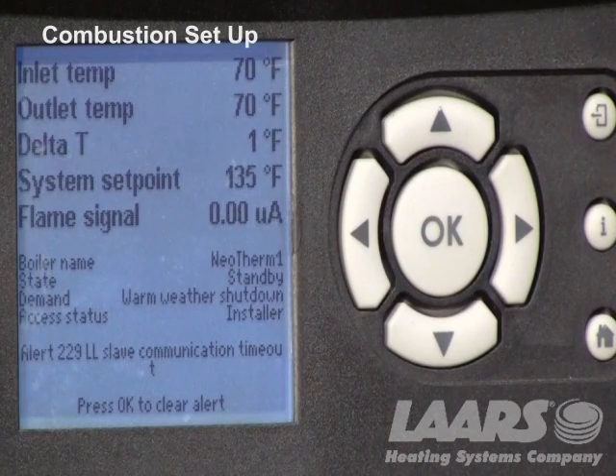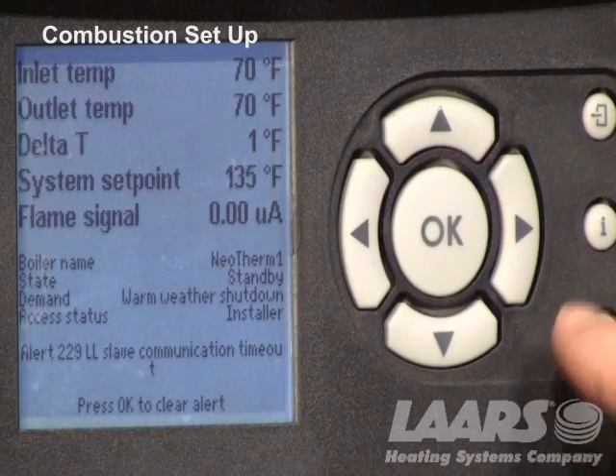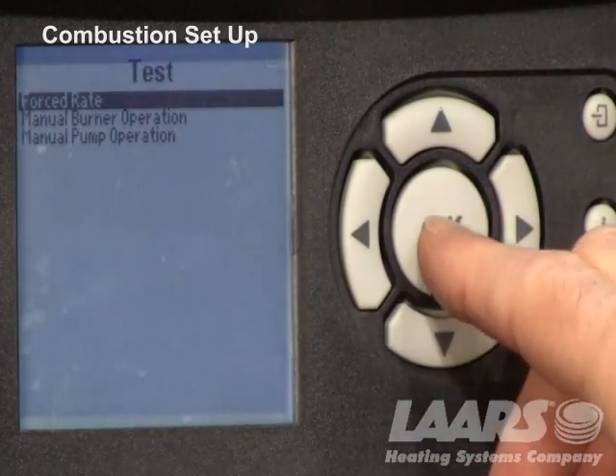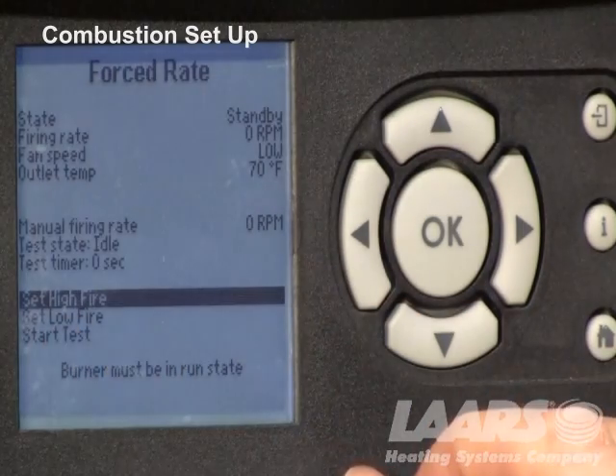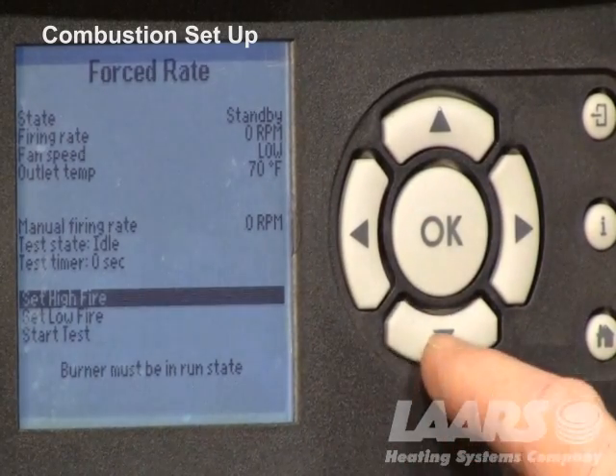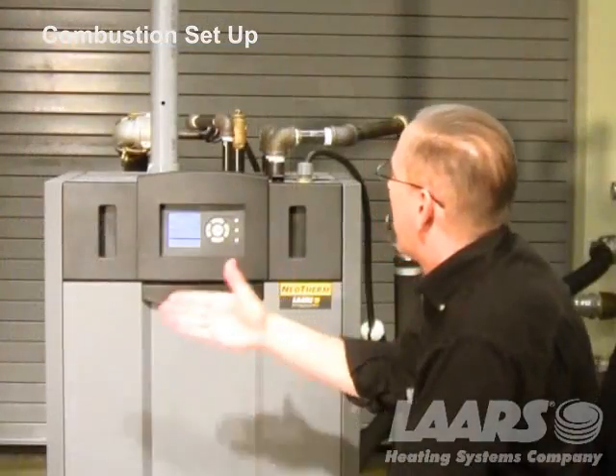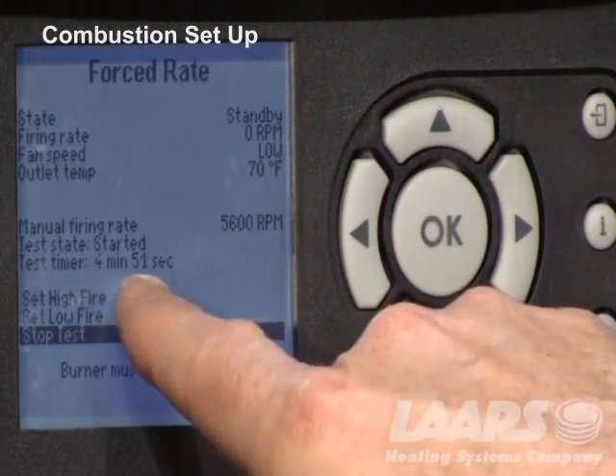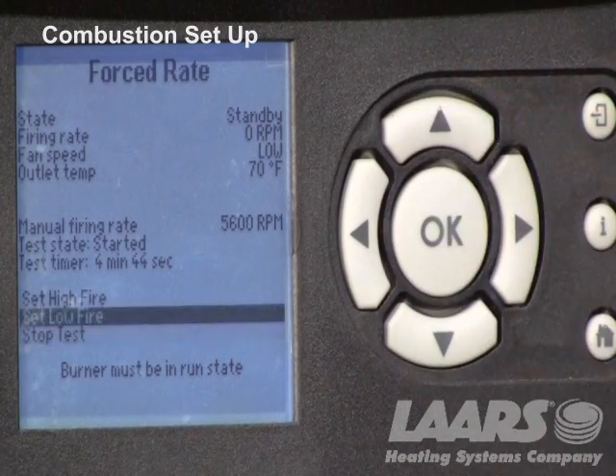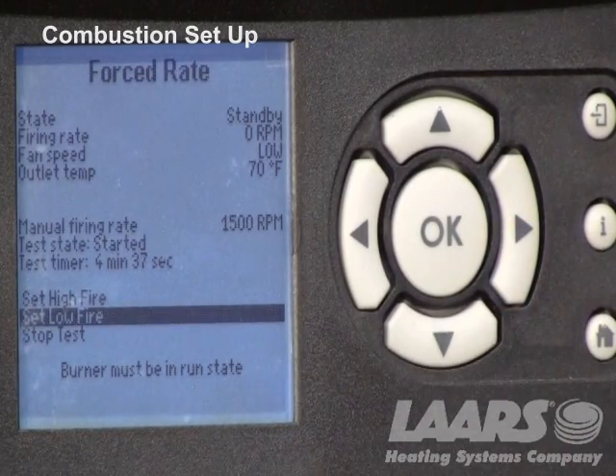Lastly, we want to do the combustion setup, which we talked about on the earlier screen. Press the eye icon, highlight test, press test, choose force rate, press okay. It's already highlighted for high fire — the burner must be running for this to take place. Press okay, scroll down to start test, press start test, and here's the test timer counting backwards from five minutes. You now have approximately four minutes and 51 seconds to do your combustion test and adjust your high fire. When done, use the up arrow to highlight set low fire, press okay, and go in and adjust your low fire setting.